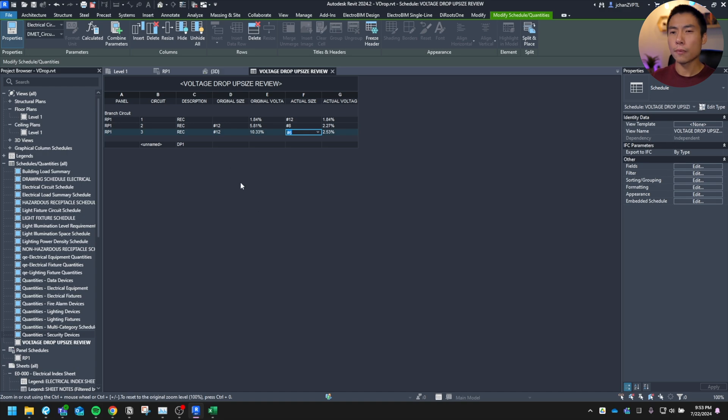So that's pretty cool, right? So I don't have to put in an exact load at the time or ever really. You can just run all your calculations based on 80% of your upstream feeder size, and that should give you a pretty robust design so that whatever they plug in later on down the road on the roof, be it a pressure washer, a big fan or motor, whatever. Once they plug that in, it's just going to work.